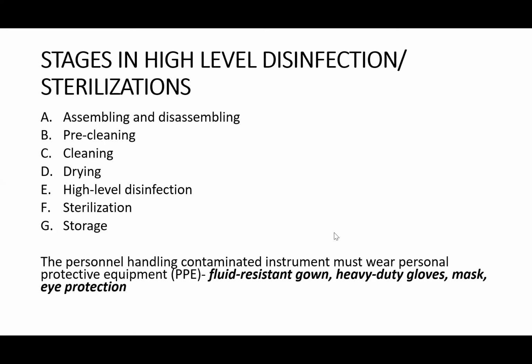Now, after understanding all the principles of what cleaning is, what sterilization is, what disinfection is, and the various levels of disinfection: high-level disinfection, intermediate-level disinfection, and low-level disinfection, you should understand the stages for high-level disinfection or sterilization. Because when you use an instrument, you have to follow a specific process to sterilize that instrument. You should also know that the personnel handling contaminated instruments must wear personal protective equipment, PPE: a fluid-resistant gown, heavy-duty gloves, mask, and eye protection.